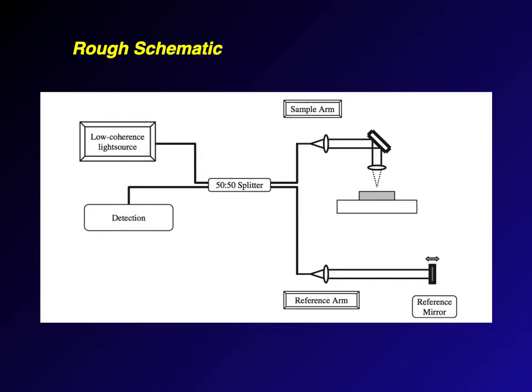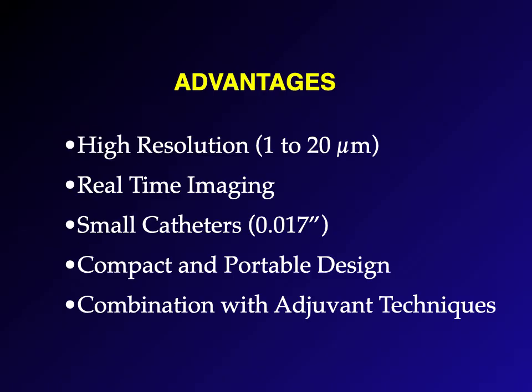In the sample arm there's a microscope, but this could be an endoscope. Because we're using fiber optics — in non-transparent tissue, unusual fiber optics — it's very small. Catheters can be engineered around the fiber optic that is 120 microns in diameter, and can be brought down to 80. The core on that fiber is only 8 to 9 microns.